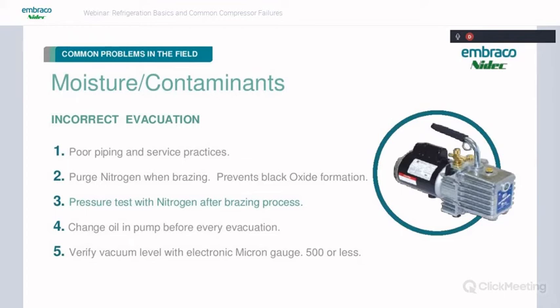And we really need to verify that vacuum level with an electronic micron gauge. We want to see 500 microns or less and pull it for 20 to 30 minutes at that. And that should ensure that you're getting all the moisture out of there.